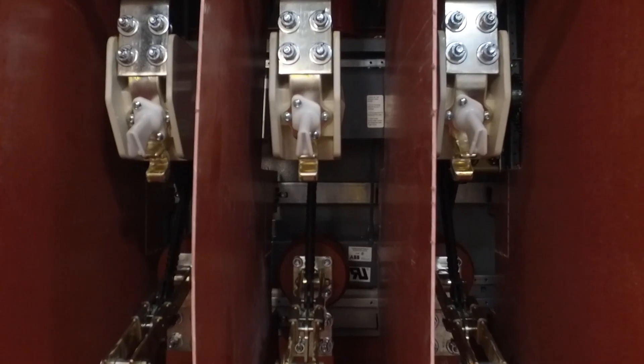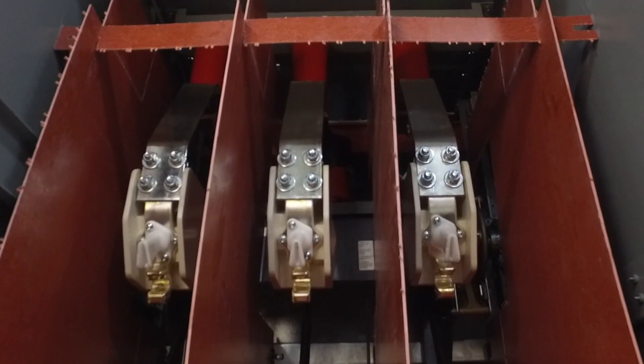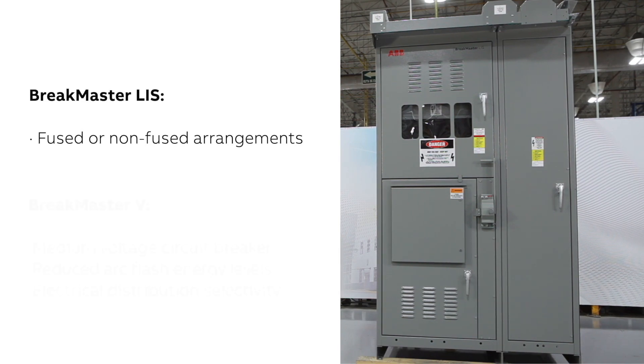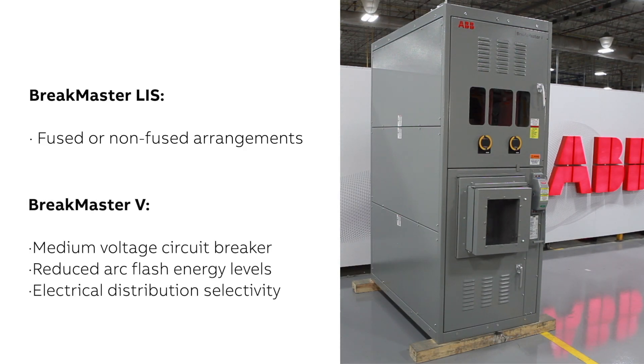Both BreakMaster LIS and BreakMaster V have an enclosed two-position open-close three-pole gang-operated air interrupter switch that uses a spring-charged mechanism. BreakMaster LIS is available in fused or non-fused arrangements for fault current protection, and BreakMaster V features a medium voltage circuit breaker for reduced arc flash energy levels and electrical distribution selectivity.